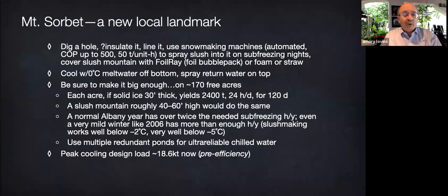So based on simple cost estimates validated from a Swedish project, we found it should cost less upfront, including the front-end cooling towers for pre-cooling, than an equivalent chiller plant. So the seasonal ice pond approach was invented by my late friend, the nuclear weapons designer, Dr. Ted Taylor. It worked nicely a few decades ago on an office building in New Jersey and at a cheese factory in New York State near the proposed chip fab.